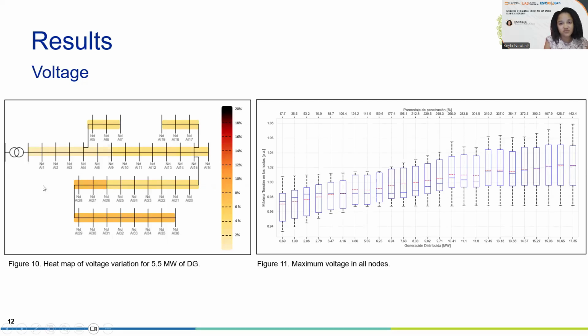We can see that for a penetration of twice the load connected to the circuit, in this case 5.5 megawatts, there are variations of up to 10%, mostly at the end of the circuit. So there is a need to monitor the voltage, especially in these sites, so that the protection schemes can be adapted or changed according to these new parameters of operation. Also, the maximum voltage registered in all nodes for all penetration levels does not exceed regulation, so there is no hosting capacity associated with the voltage performance index.